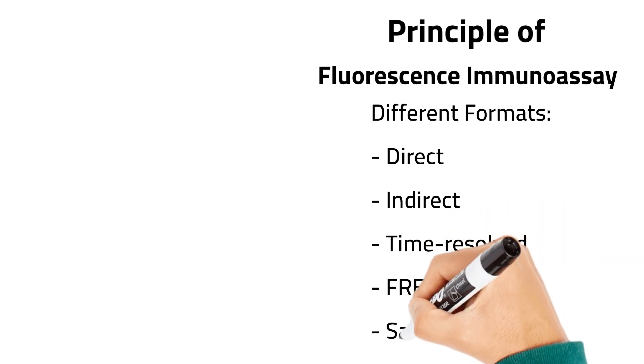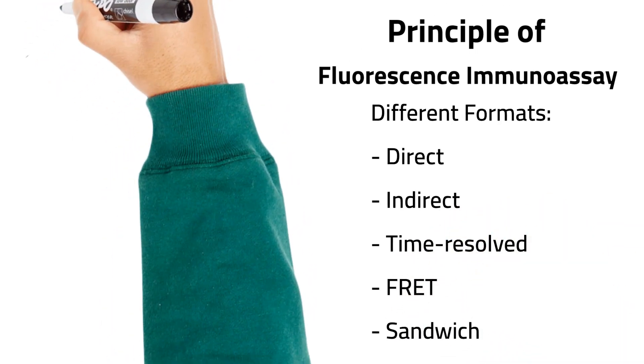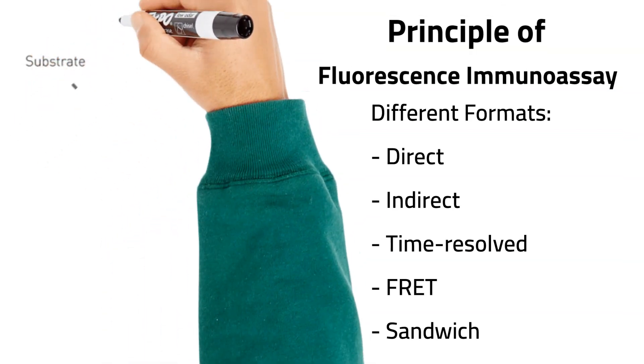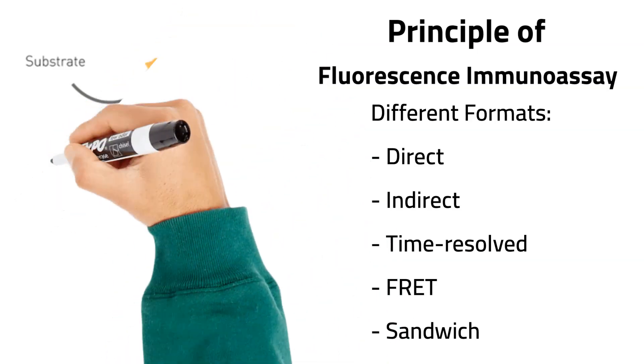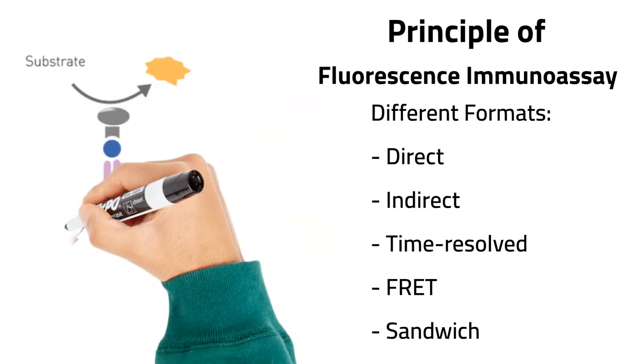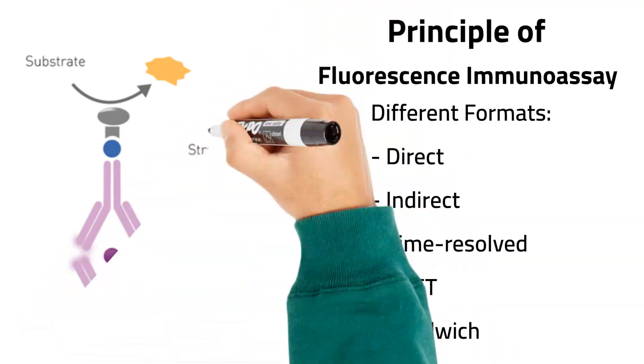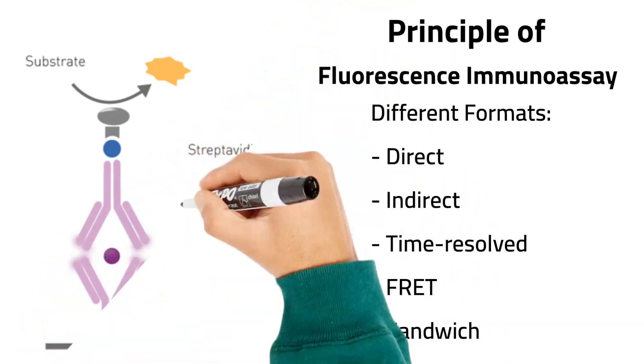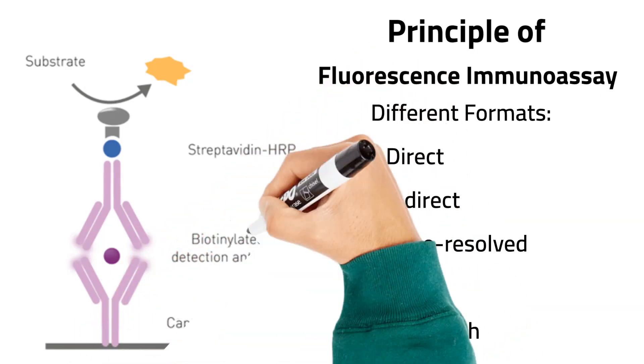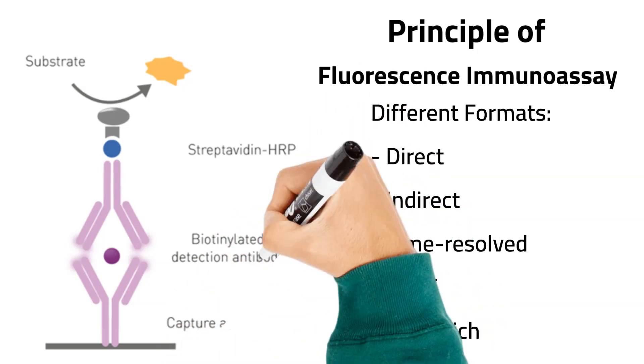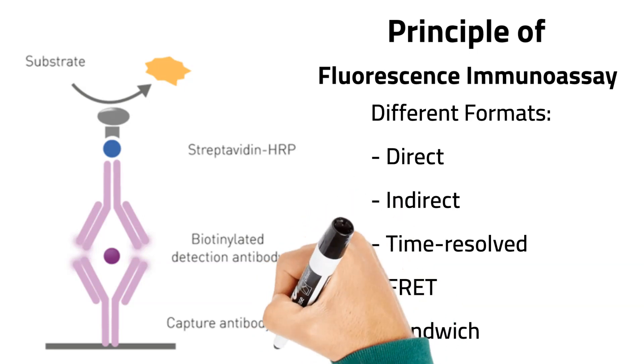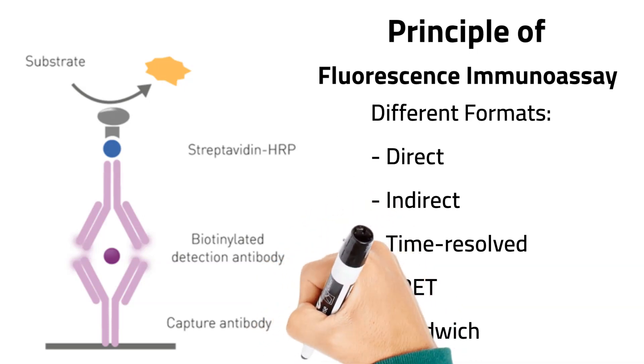The sandwich method is a widely used format which involves the capture of the target molecule by a specific antibody immobilized on a solid surface. A detector antibody labeled with a fluorescent molecule then recognizes a different epitope on the captured target molecule, thereby forming a sandwich complex. Upon excitation of the fluorescent probe, it releases energy in the form of fluorescent emission, which is then measured. The intensity of the fluorescent signal is proportional to the concentration of the target analyte in the sample.